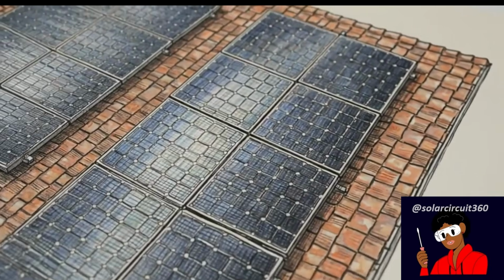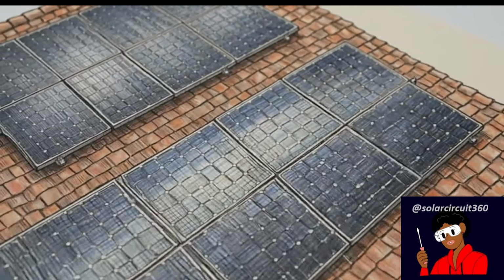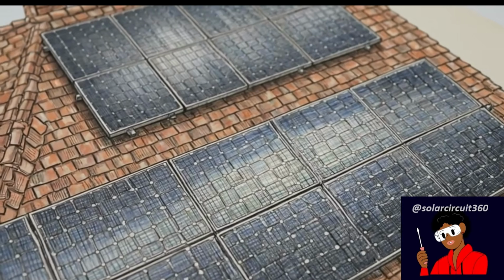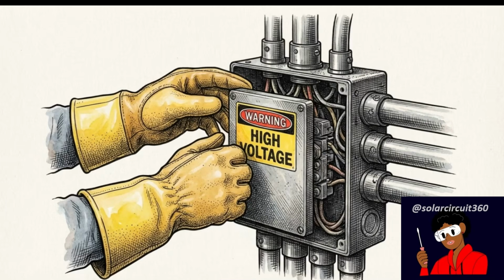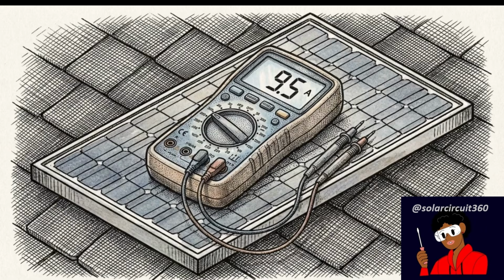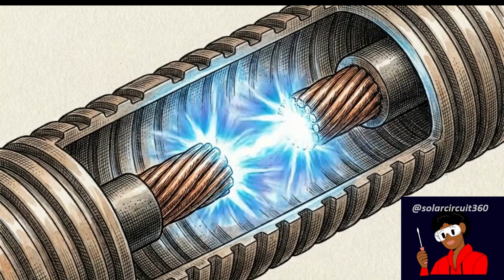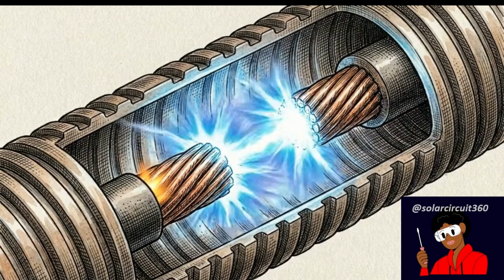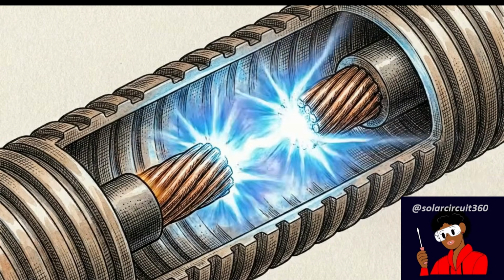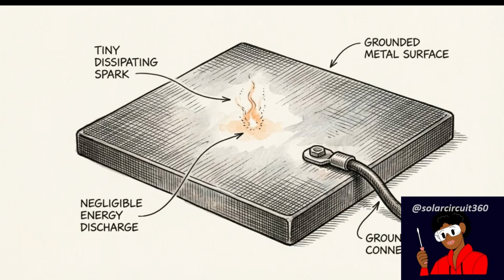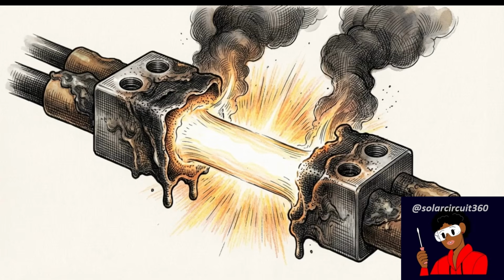Most people look at a typical rooftop solar array and see a silent, completely passive piece of technology. When building these systems, amateur installers tend to focus their safety checks entirely on avoiding standard electric shocks. They look at the relatively small current coming from a single panel and assume the safety risk is inherently low. But that assumption completely ignores a silent, highly aggressive threat hiding inside the wiring, the DC arc flash. Unlike a standard alternating current spark that flashes and quickly dies, a DC arc is a continuous electrical fire. Once it ignites, it aggressively refuses to stop.